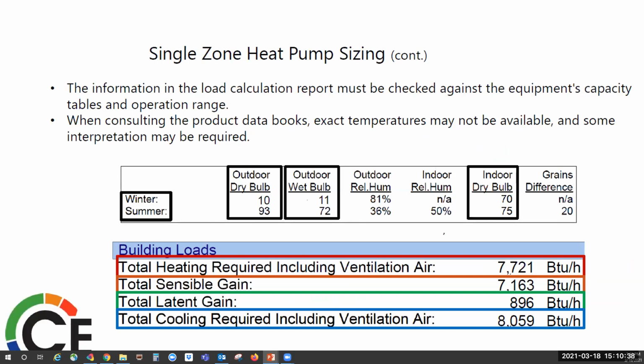Performance charts: you want to look at your product data manual, making sure you choose the equipment that'll do the job. Extreme temperature swings. In the wintertime, we have a required heat of 7,721, and our total latent heat gain here is 896. During extreme temperature swings, the efficiency on these systems can drop. For example, we had these low temperatures here in February, and in some cases our units, while they were heating, were only running 65 to 70% of that heating. Meaning, if you have a 12,000 BTU unit, you're only putting out roughly 9,000 BTUs. So take that into consideration.